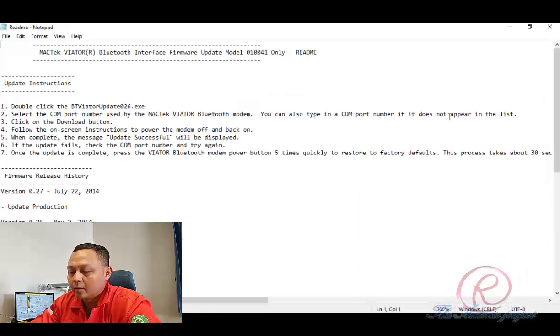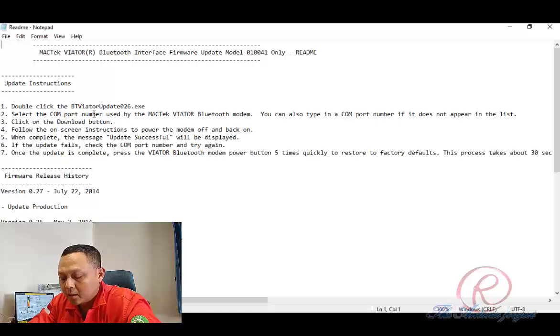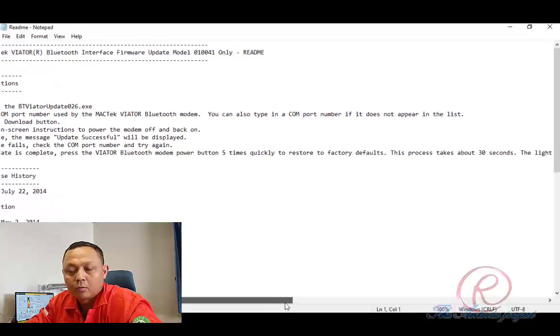First, open the folder containing the Bluetooth Viator update 027, and then open the readme text. There is a procedure on how to conduct the update. The instructions are: first, double-click the BT Viator update 026 executable. Then, select the COM port number used by the MACTek Viator Bluetooth modem, or type in the COM port number if it does not appear in the list. Number three, click the Download button.